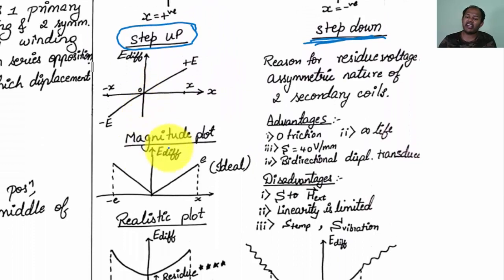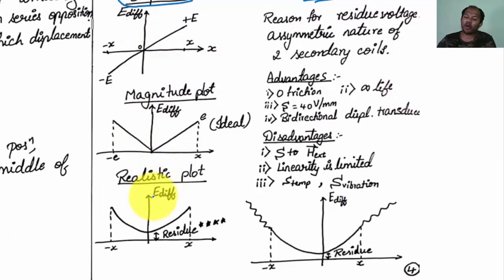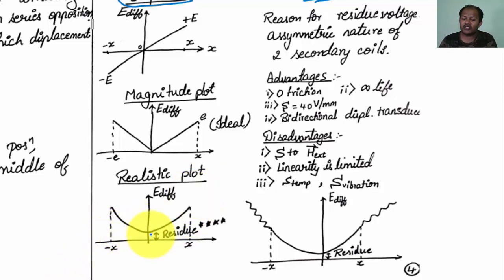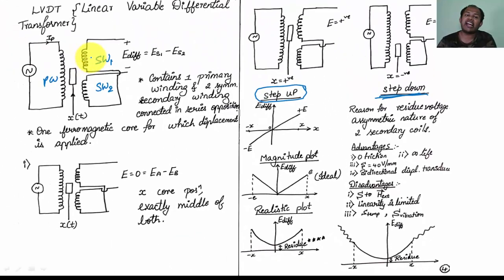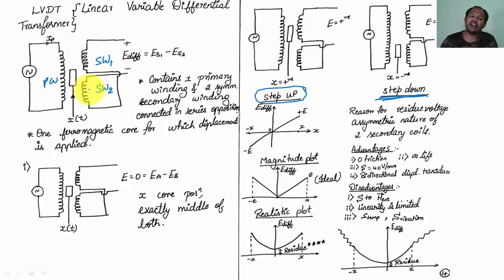The output curve is a magnitude plot, but the realistic plot has a bend-type curve because it is not exactly linear. The point at null position is not exactly zero — you will get a residue. The reason for residue is the asymmetric nature of the two secondary coils: the number of turns, material characteristics, and winding area of the two secondaries cannot be guaranteed to be identical.